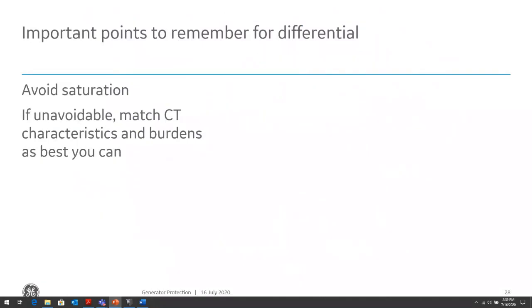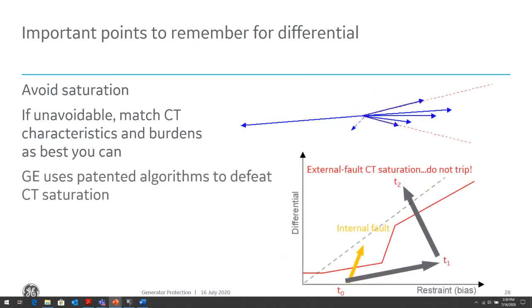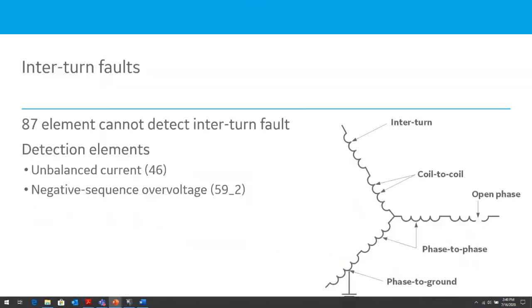The main points to remember for differential is to avoid saturation, size the CT properly. But if unavoidable, then match the CT characteristics and burdens as best you can and take care of it in the relay settings. We do use a patented algorithm to defeat CT saturation, which is we detect CT saturation, and if we do detect CT saturation, we use the directional principle to also say, is the fault within the zone or not? If it's not within the zone, then we won't trip. If it's within the zone, then we trip, so that we'll be able to deal with CT saturation issues.